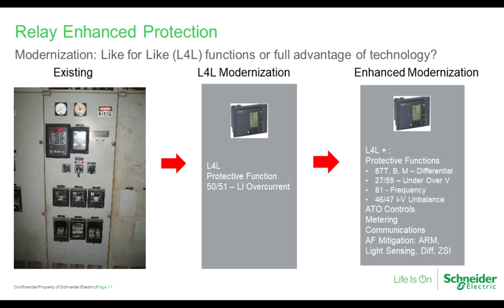The relay enhancement protection, modernization, like for like functions of full advantage of technology. You can see in this picture the existing relay panel for a switchgear door. This happens to be an old Allis Chalmers, but you can see the mess of relays on that door and also the metering. You can see an old meter, old analog meter, a new digital meter. You can see old electromechanical relays at the bottom, and that door is just full of relays.